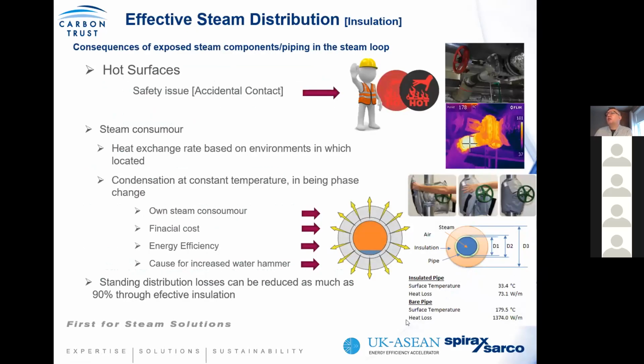When we start looking at effective distribution, there are two sides to it. You'd see plenty of cases where the pipes would be insulated, but isolation valves and the like would not be insulated. If you were to look at it with a thermal imaging camera, you could see very quickly the heat that's being radiated from the exposed pipework. So there are two kinds of areas: health and safety. There's a risk of accidental injury if someone was to come in contact with it. So scalding and burning.